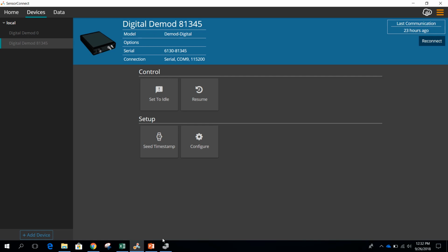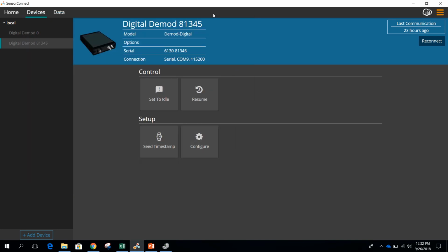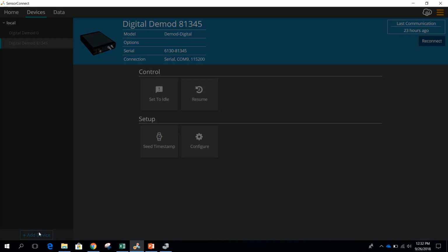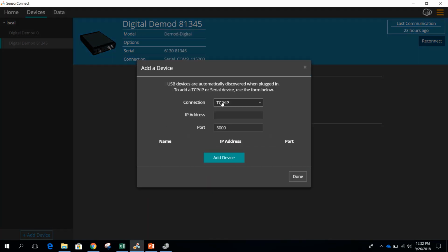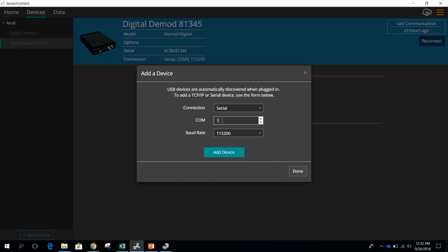I will now be showing you how to connect the DMOD digital device to Sensor Connect. First, I am opening Device Manager to see that the DMOD is connected to serial port COM9. Then I will be adding a new device, selecting serial, importing COM9, and keeping the standard baud rate of 115,200.